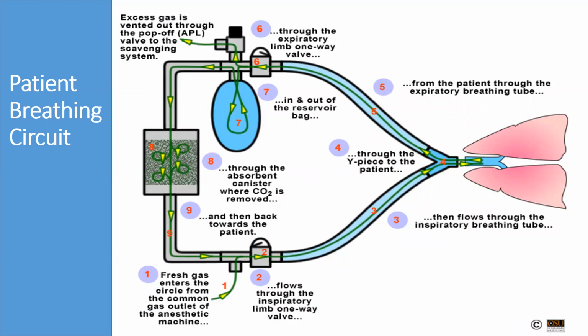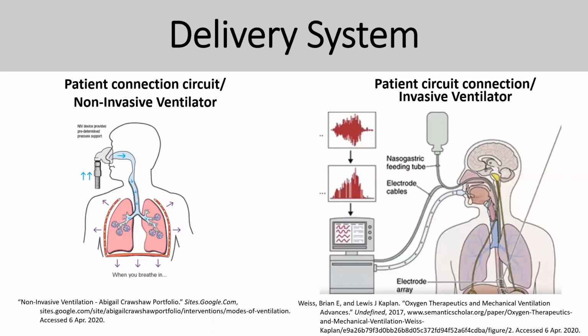Okay, the following one is a patient breathing circuit. These are commonly seen in the anesthesia machine, but the practice is almost similar; the only difference is you've got an absorber, all that, and these are closed loop circuits. A closed loop circuit is basically where you breathe in and breathe out, and it is going to go around again with some fresh gas, all that. So this is how the system works. Okay, delivery system. There are two types of delivery system. Normally they use non-invasive and invasive types of connection for the breathing.